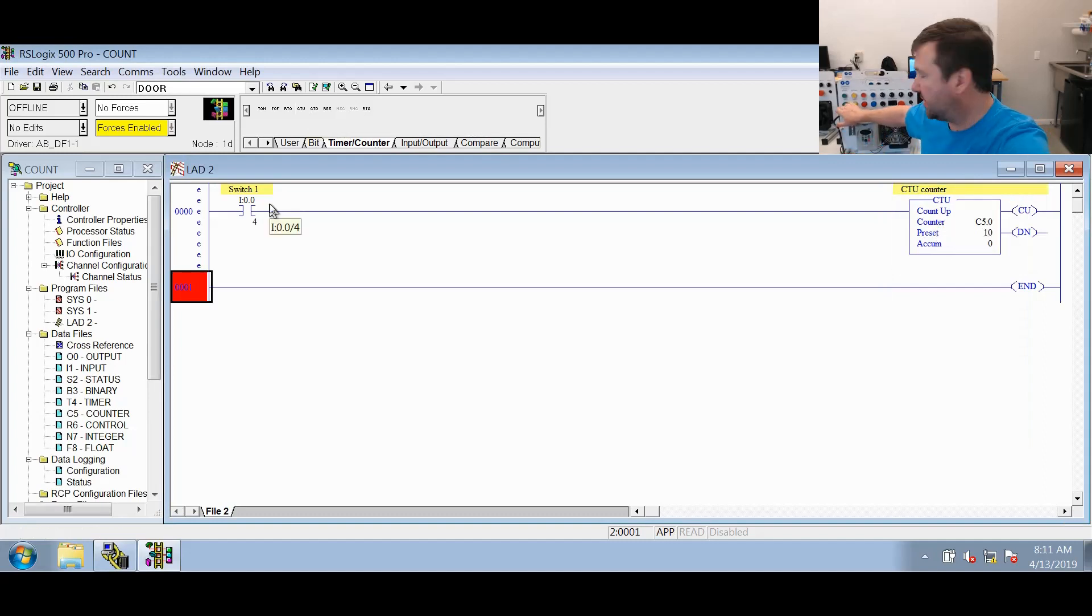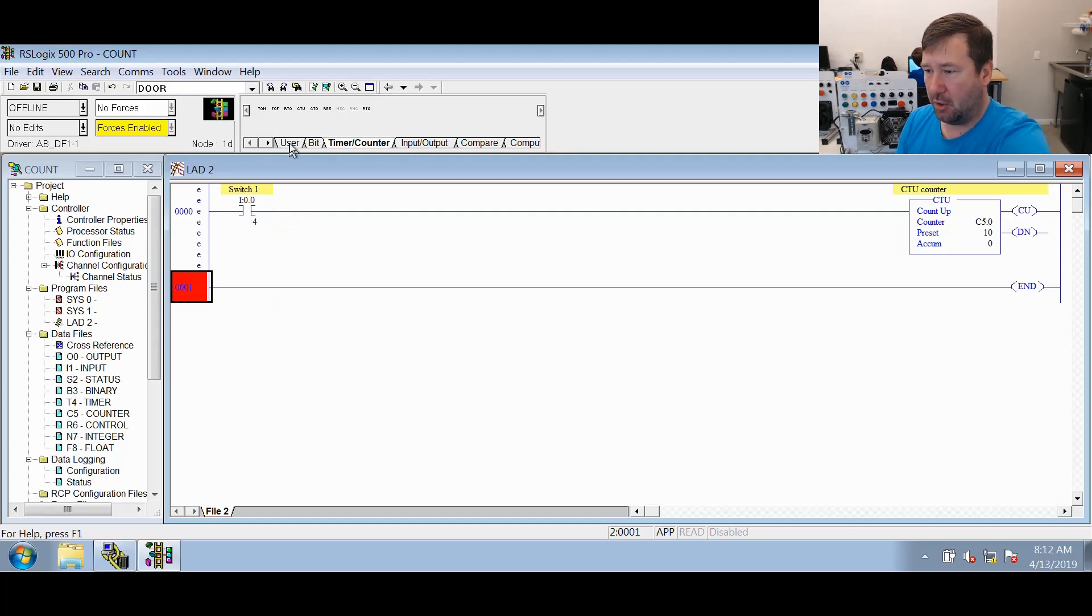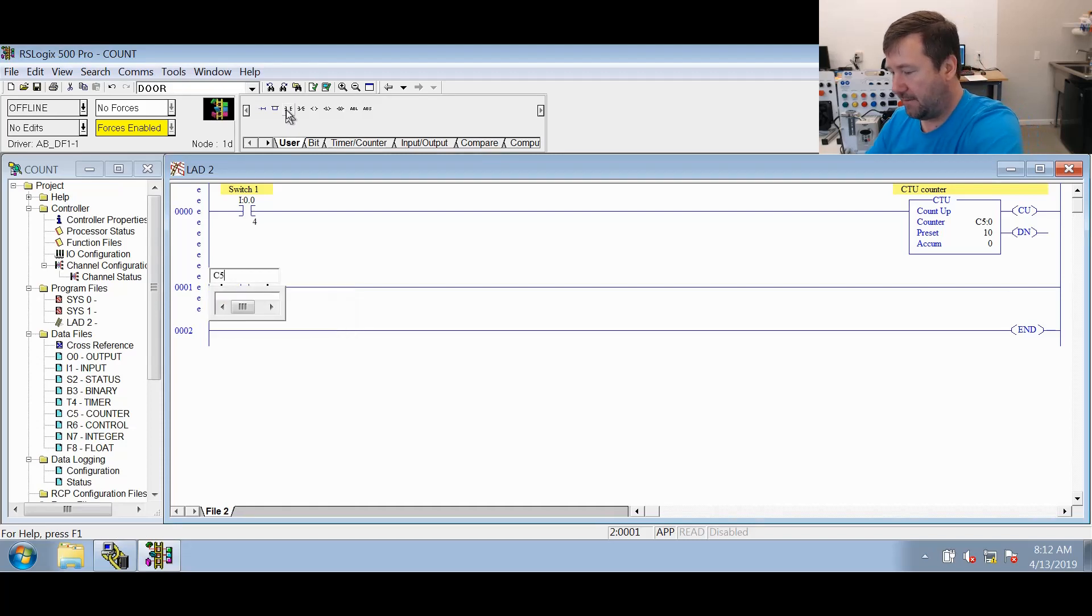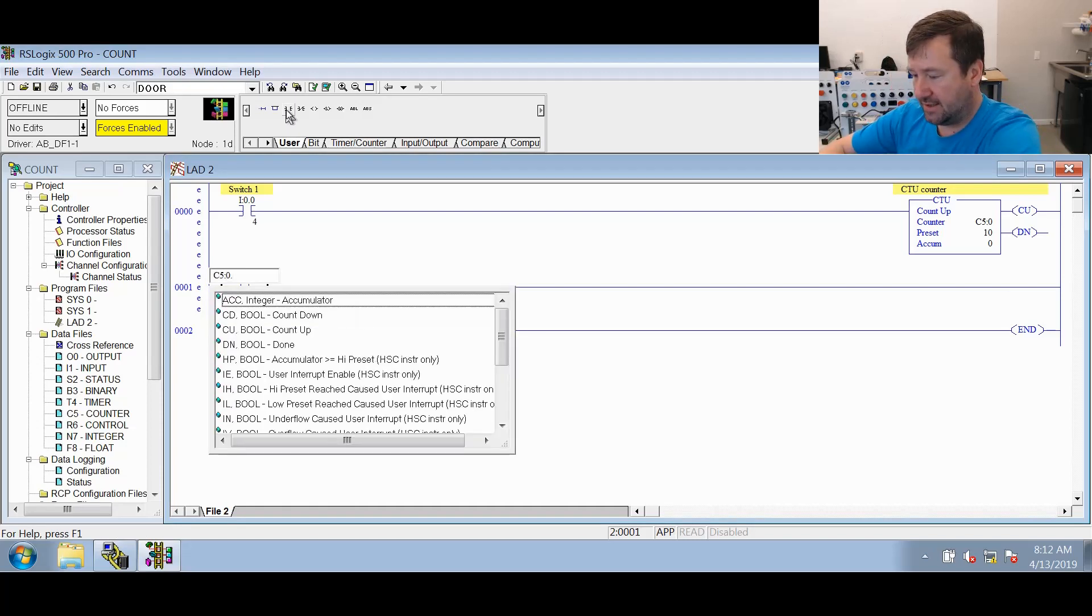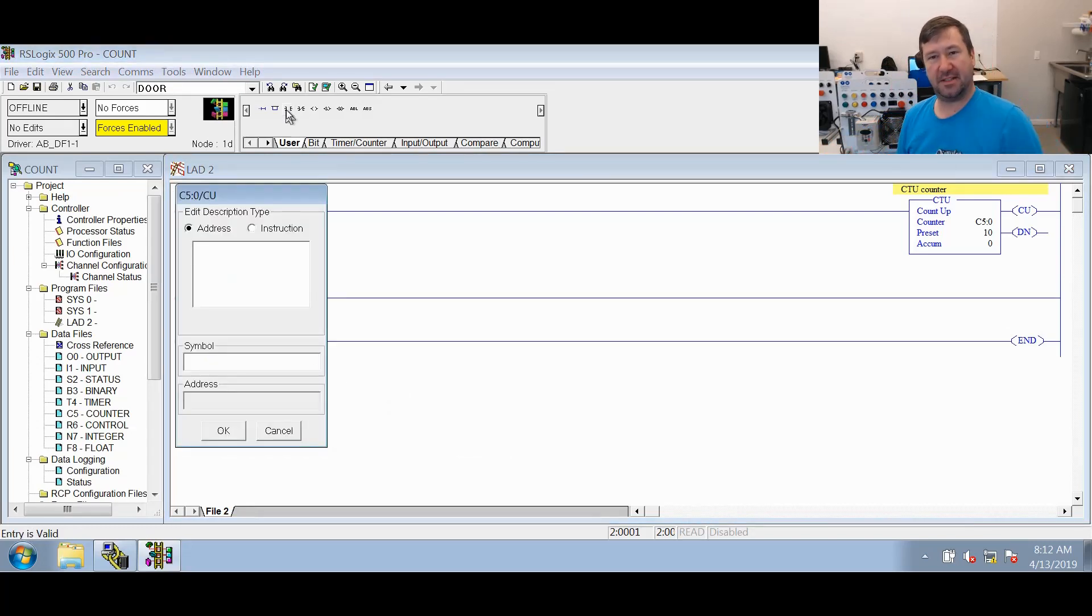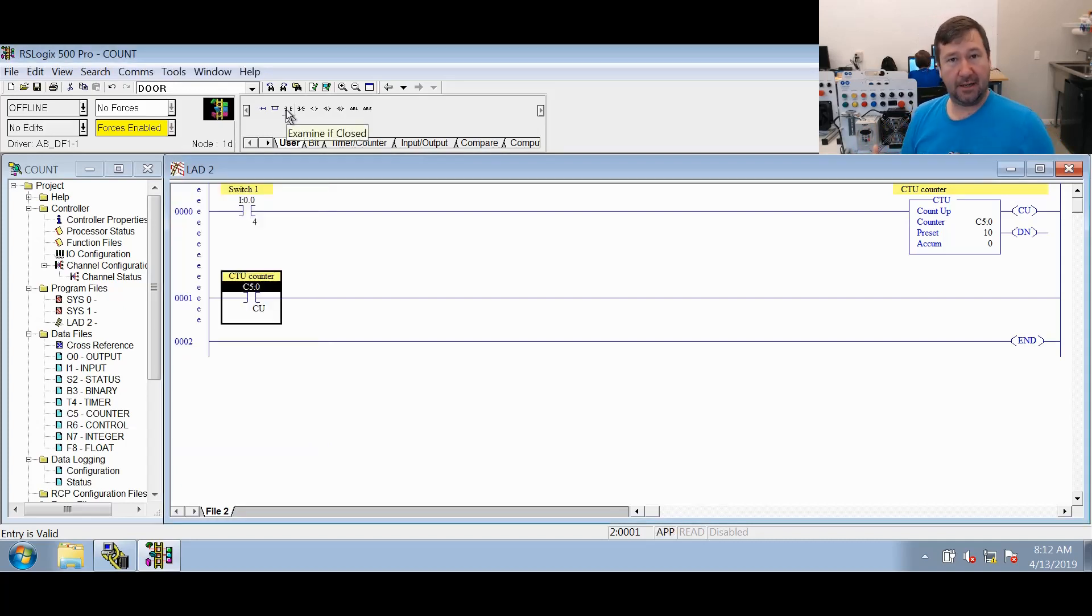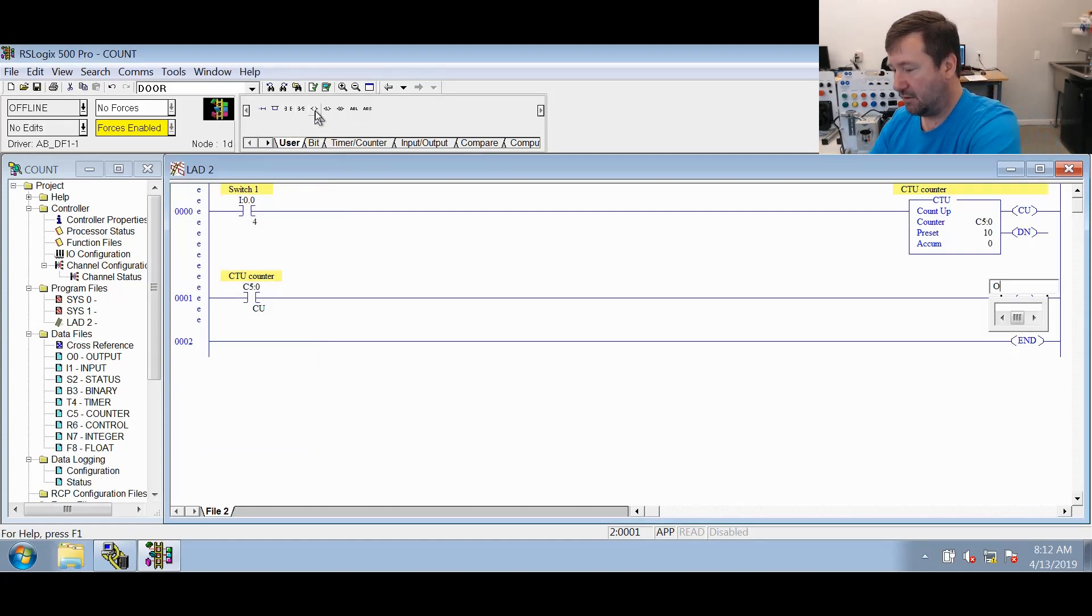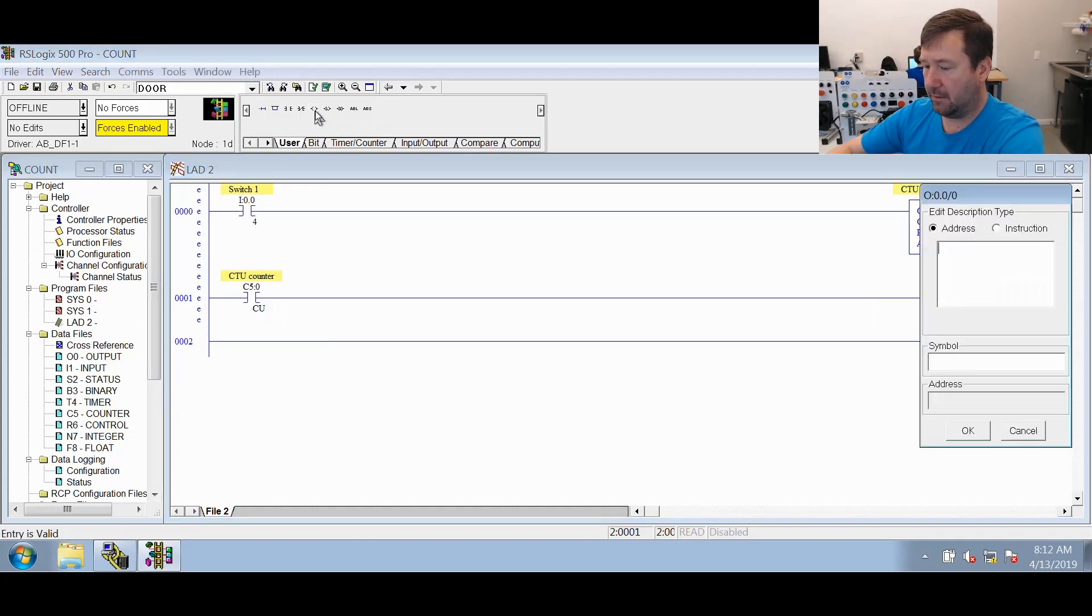Now we're going to tie the counter bits to these lights just so we can get a visual of when they're turning on. We're going to go back to our user tab and select XIC instruction and put C5:0.CU. We won't put a description in, just the same as the timers. If you don't put a description in a child element, then it will take the description of its parent element. We're going to assign this to the green light, which is O:0/0, and we'll just call that the green light.